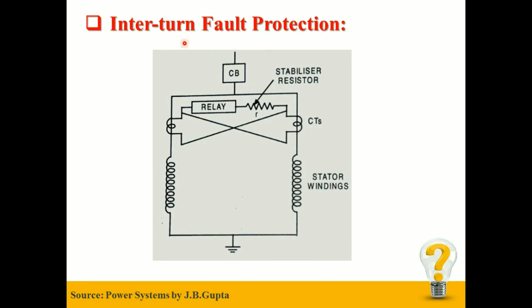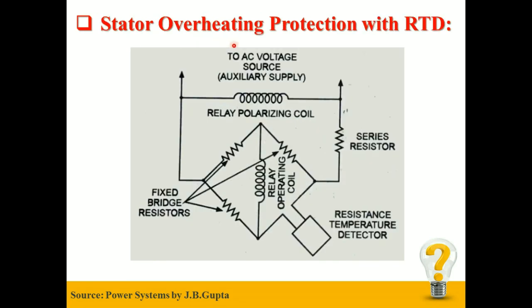Stator Overheating Protection with RTD: Stator overheating is generally caused by sustained overloads or by cooling system failure. An electrical overcurrent relay cannot sense the winding temperature accurately because temperature rise depends on I²RT and also on cooling. Electrical protection cannot detect failure of the cooling system. Therefore, the general practice is to embed RTDs — that is, Resistance Temperature Detectors — or thermocouples in the slots below the stator coils for protection against overheating.